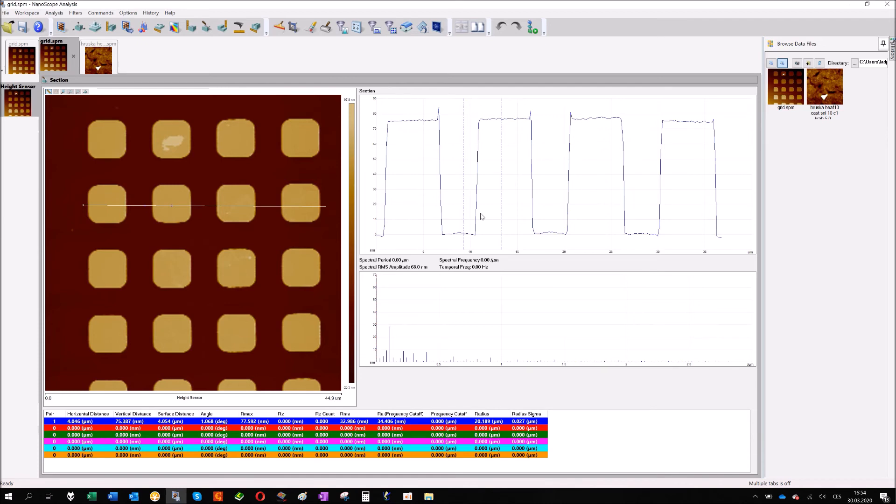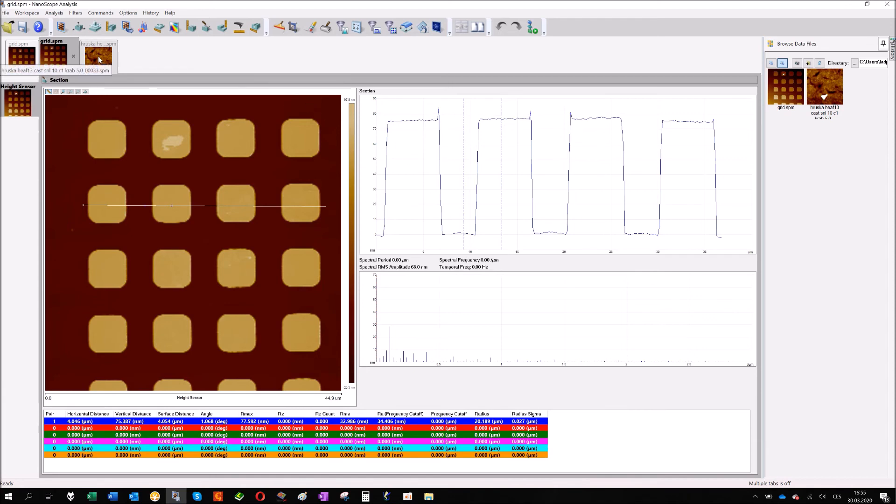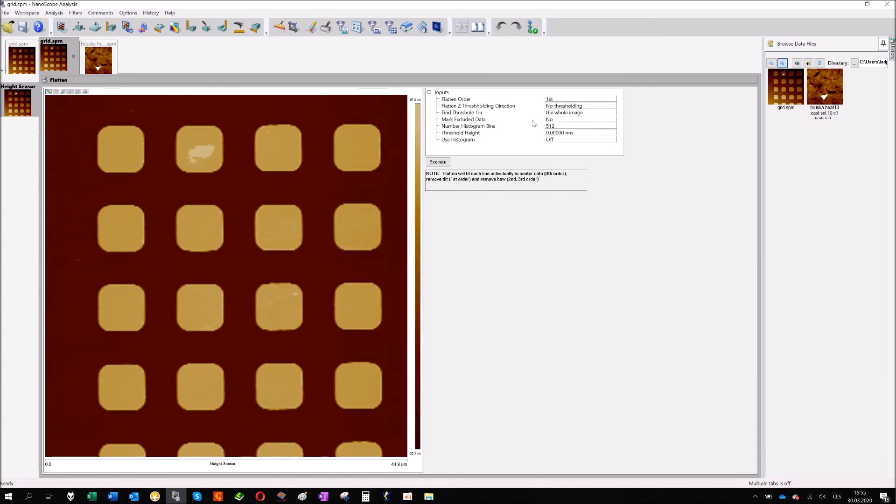If you know something about the sample, you may get an idea that it will be much better to use for the flattening the position of the sample which are here at the bottom, the substrate. Typically you have a substrate and you have some nanoparticles on the substrate, and you want to use the substrate for calculation. Yes, as before, as we did here, you can exclude the data manually, but you don't want to do that for thousands of particles, it will not be even possible. For that there is also some other parameters for flattening and it's called thresholding.